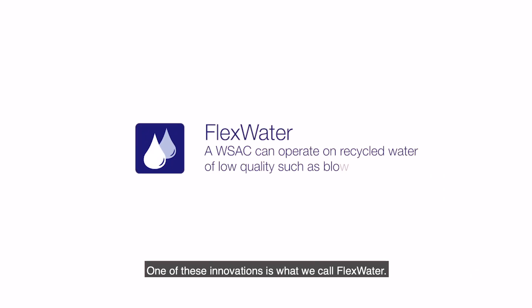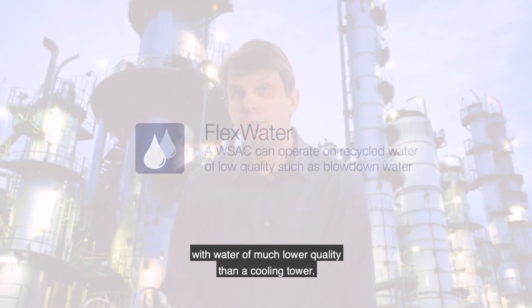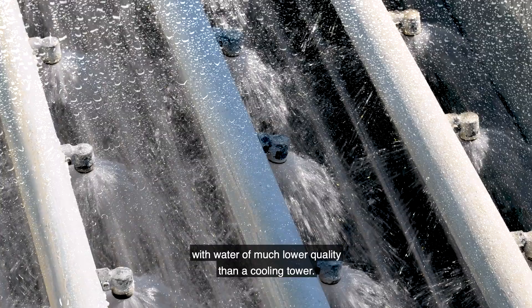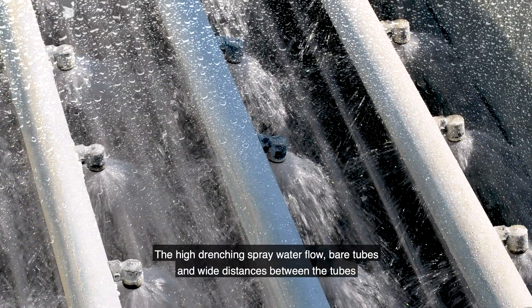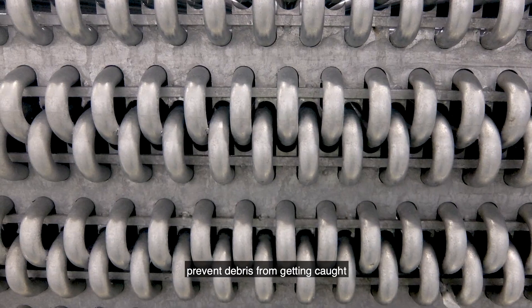One of these innovations is what we call FlexWater. Thanks to its special design, a wet surface air cooler can operate with water of much lower quality than, for example, a cooling tower. The high drenching spray water flow, bare tubes, and wide distances between the tubes prevent the debris from getting caught.